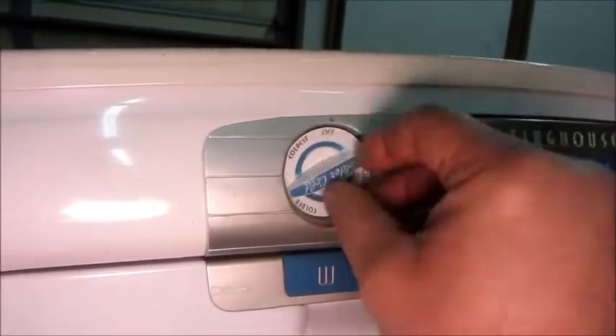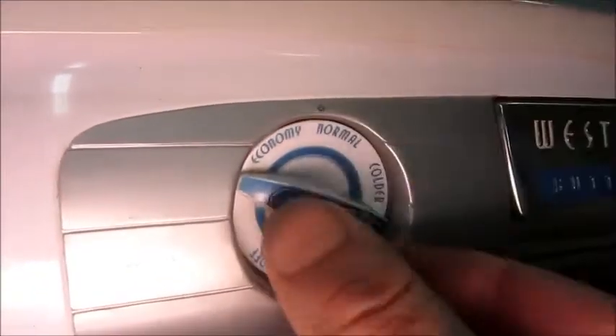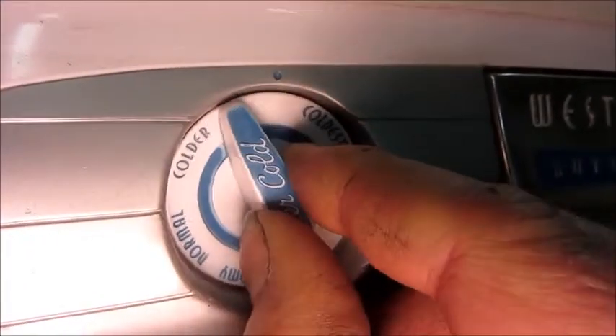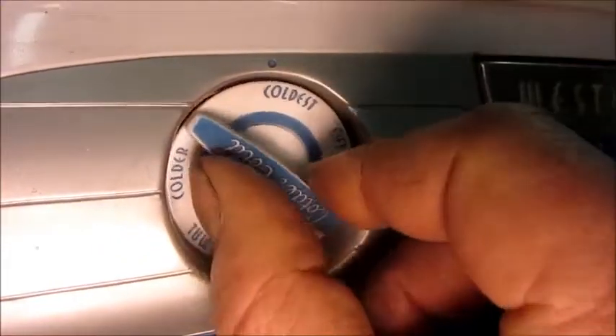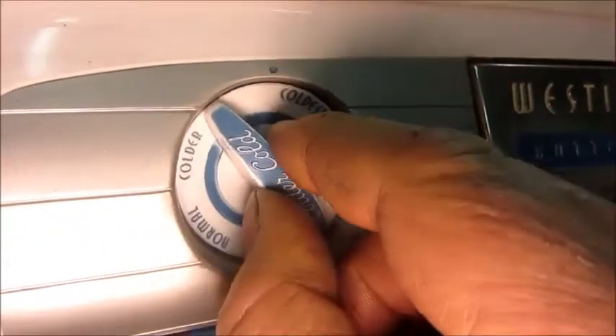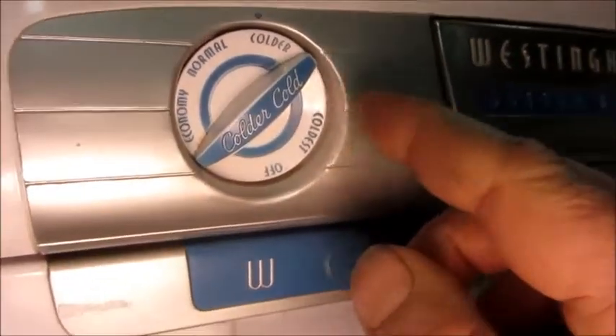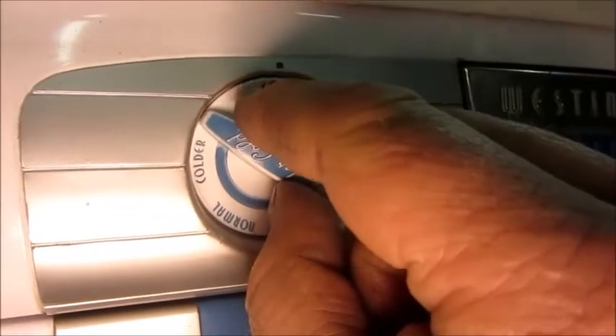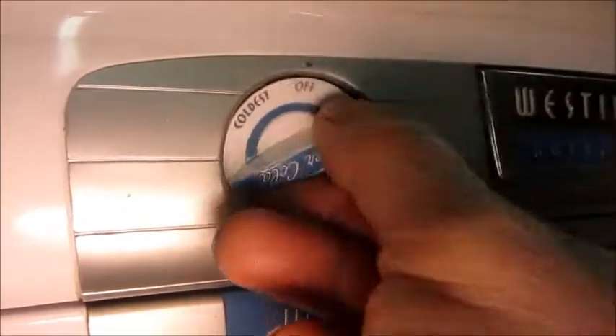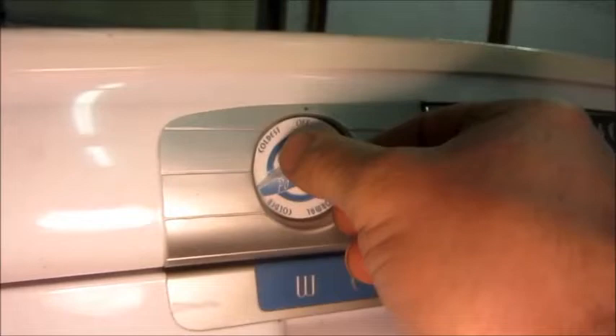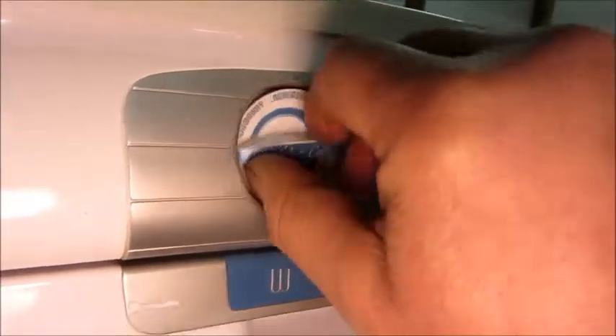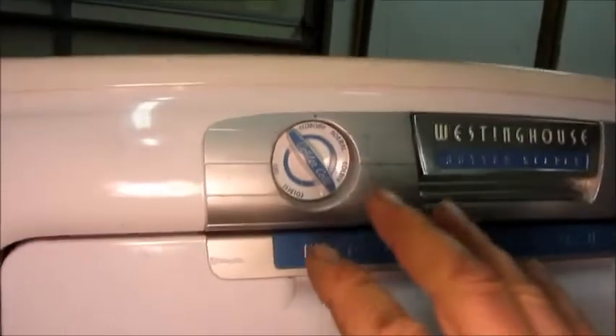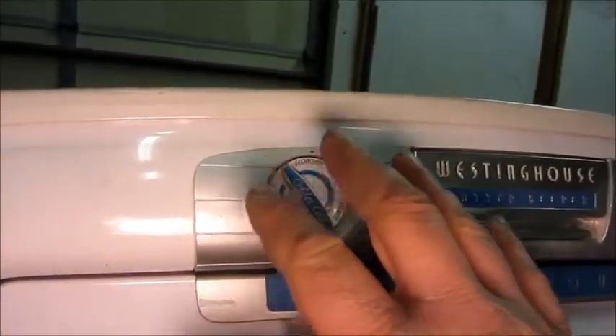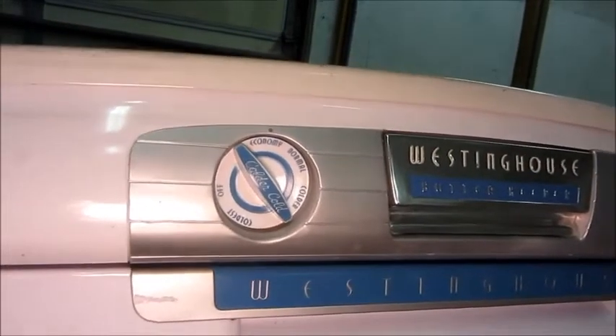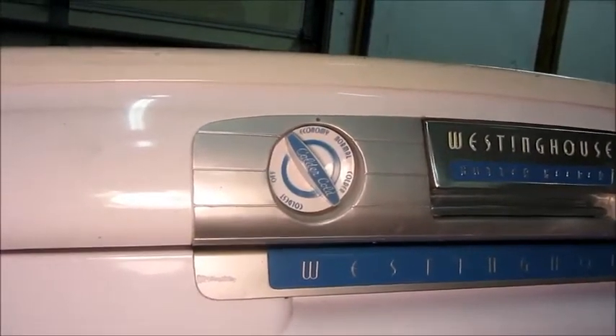If I turn the control all the way to the coldest, it finally would have clicked on there. So it's the temperature of the evaporator is almost to the full cold for this control. And that does tell me that the thermostat bellows is working. Now Westinghouse is unique in this era in that this thermostat is a unitized thermostat and motor start relay. So the fact that the compressor wouldn't run, probably the problem is right behind here, or some wiring.